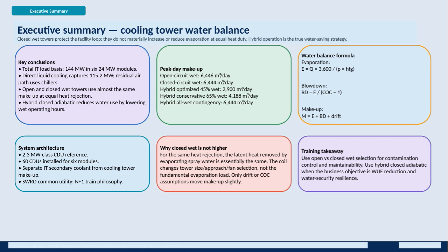Looking at the key conclusions, the total IT load is 144 megawatts, divided into 6 modules of 24 megawatts each. Direct liquid cooling handles 115.2 megawatts of that load, while the remaining heat is managed with chillers in the air path. Both open and closed wet cooling towers use almost the same amount of makeup water when rejecting equal amounts of heat. However, hybrid closed adiabatic systems reduce water consumption by cutting down the hours that wet cooling is needed.